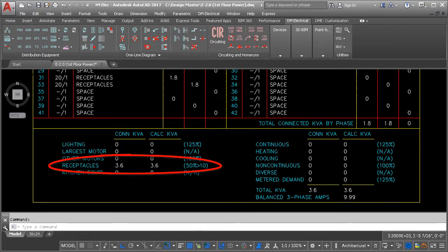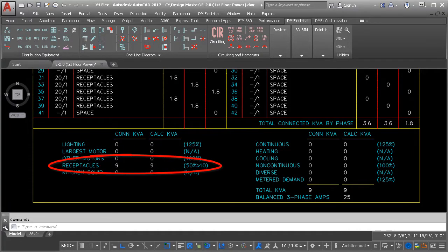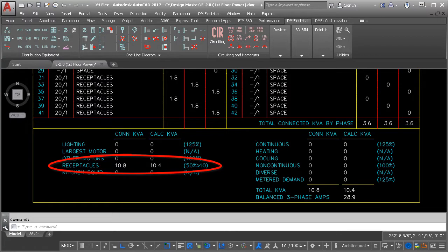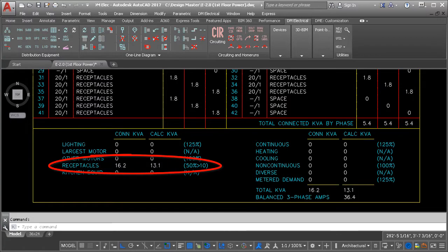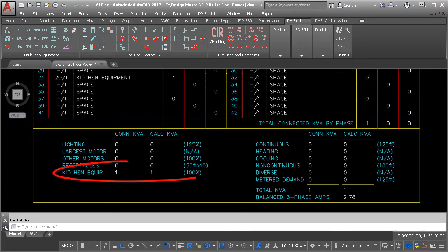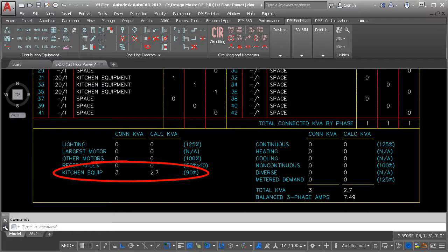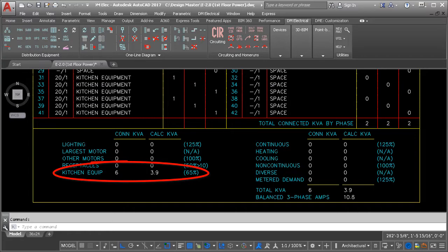Lots of receptacles? Anything over 10kVA is calculated at 50%. Kitchen equipment? The demand is calculated based upon the number of connected devices.